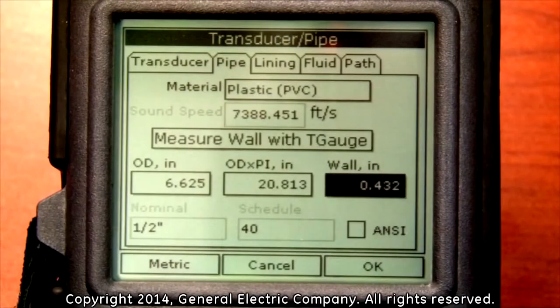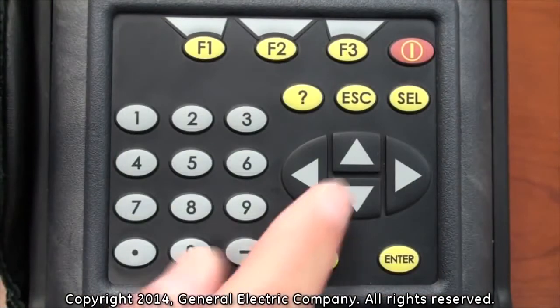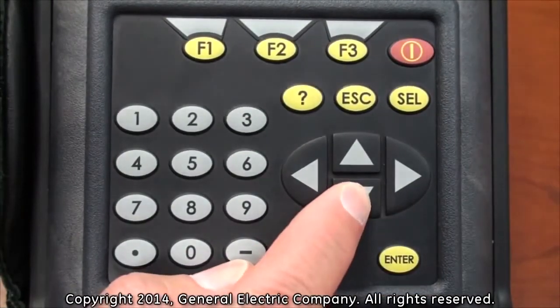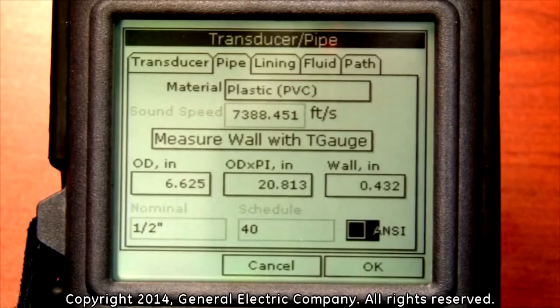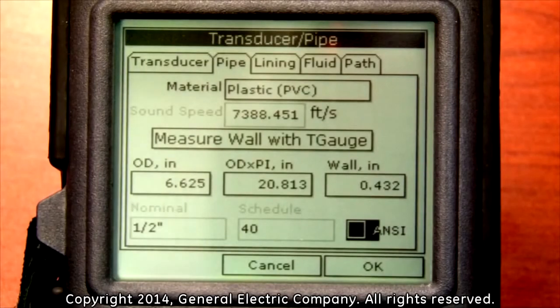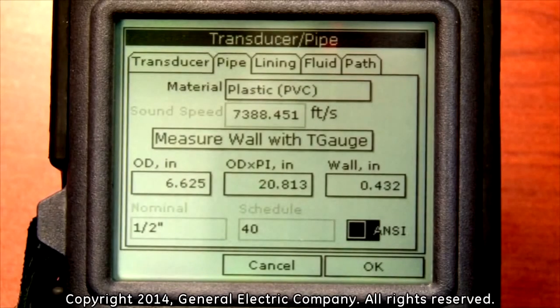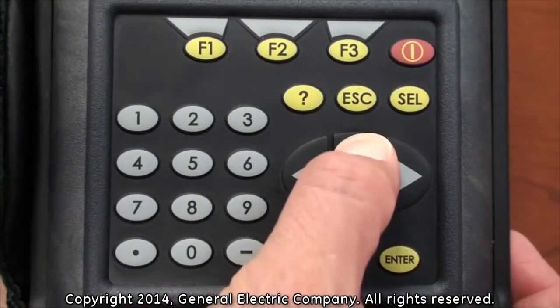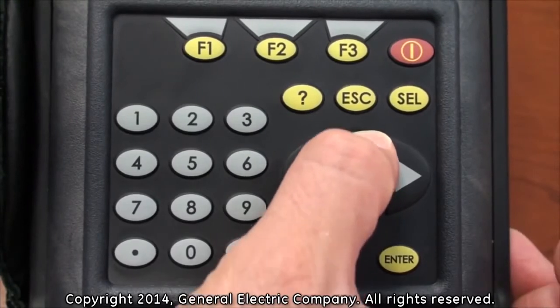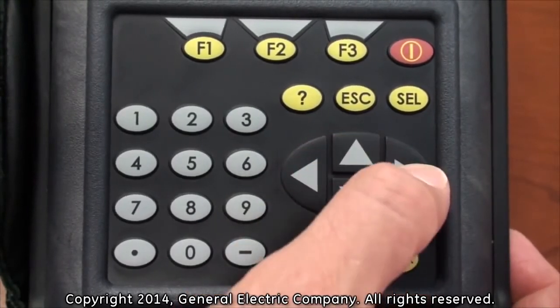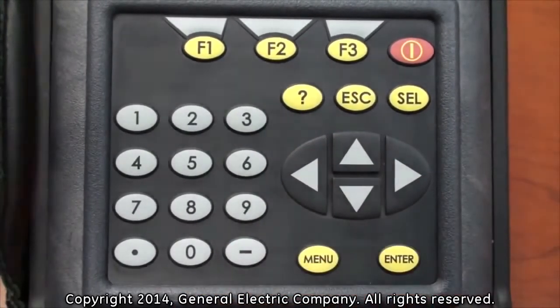If ANSI data is available and being used, you can press the down arrow key to highlight the ANSI option and press Enter to select it. You will then be able to use the arrow keys on the keypad to highlight the nominal or the schedule input fields, and then use the number keys to input the values for each. Once the pipe parameters have been programmed, use the up arrow key to go back to the top of the menu and press the right arrow key to highlight the lining menu and press Enter.